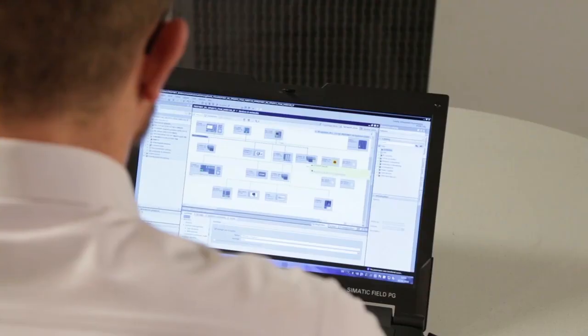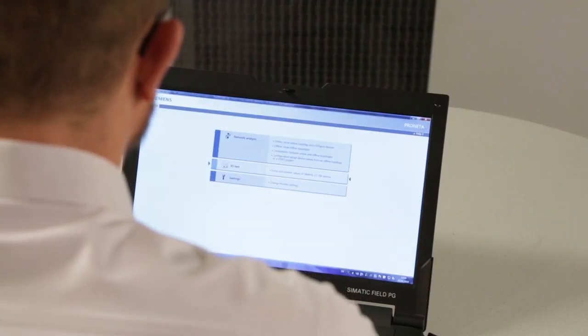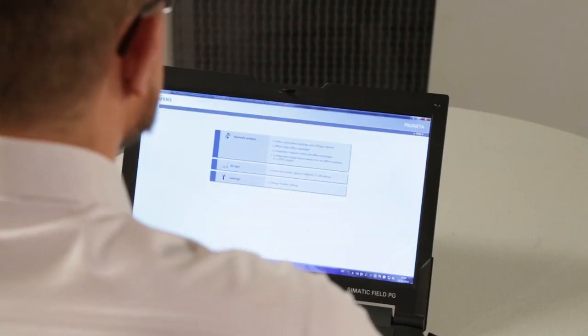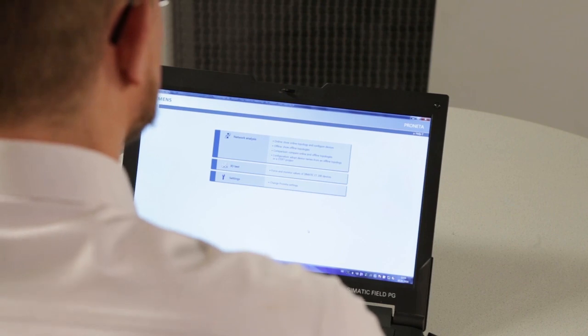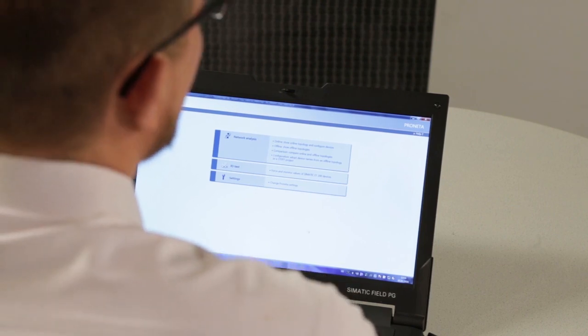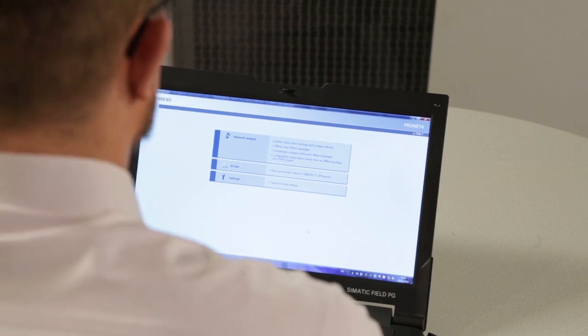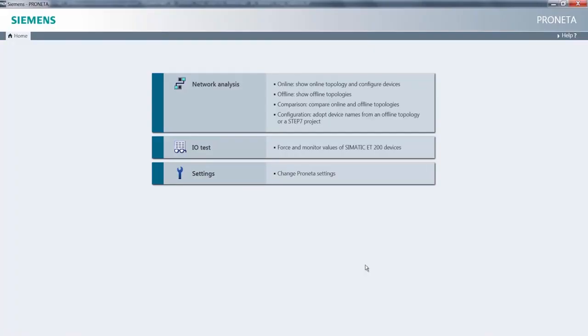Now let's take a look at PRONETA. With PRONETA, you basically have three options. The network analysis, the I/O test, and adjusting general settings in PRONETA. With the I/O test, I can switch variables, inputs and outputs without a force table and also simulate circuit breaks and other situations requiring diagnostics.